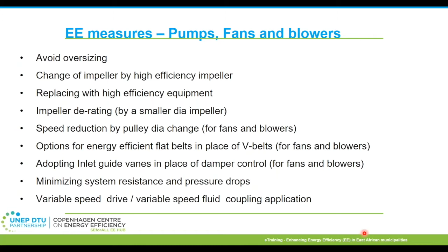For fans and blowers, these are the two types of most commonly used capacity control mechanisms. One is a damper, and then you have inlet guide vanes. Apart from this, you can also use variable frequency drives for fans. But investment cost wise, the VFDs tend to be a bit more expensive. So this is the next best efficient option you can use, where larger volumes of airflow are not required, then you can use this.